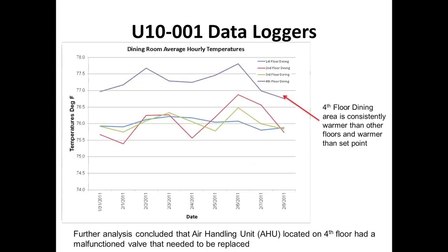We see that the first 3 floors had average temperatures that were very similar to each other. They responded similarly. The 4th floor was obviously much higher than the other floors. Going back and re-examining the equipment that's installed in the building, we know that the 4th floor did have an anomaly and that it was much higher than expected. We concluded after a further inspection that there was actually an air handler serving that floor that had a malfunctioned hot water valve on it. It was sending a lot more hot water than necessary through the air handler to the floor.